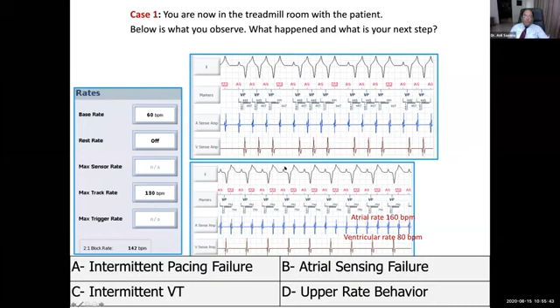Excellent. So it is upper rate behavior, as Dr. Ma has already explained beautifully, that in every dual chamber pacemaker, we have a lower rate and we have an upper rate. And in this example, we can see that the upper tracking rate has been programmed to 130. So when we put the patient to exercise, the heart rate gradually increases. And as we can see on this screen also, the maximum tracking rate is 130.